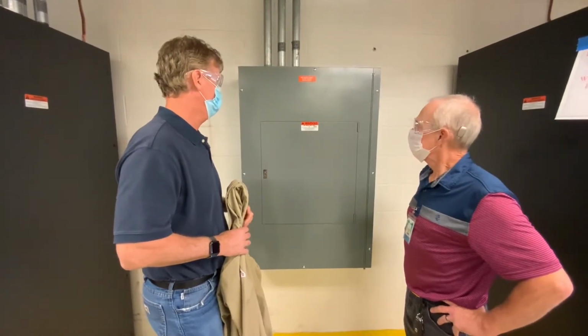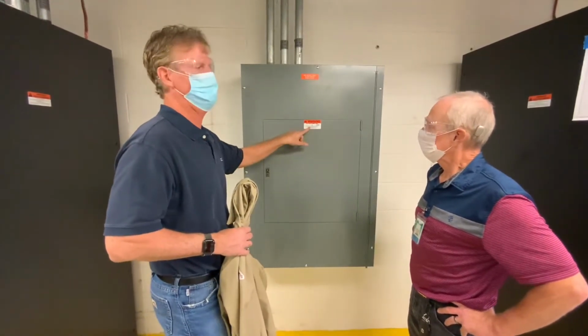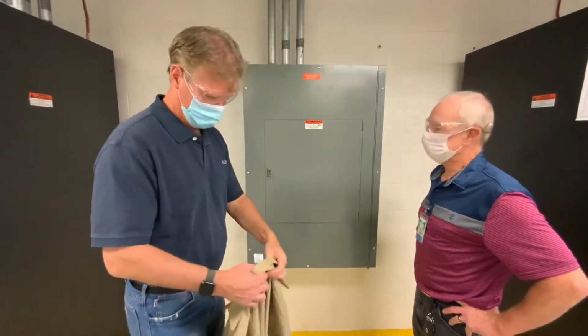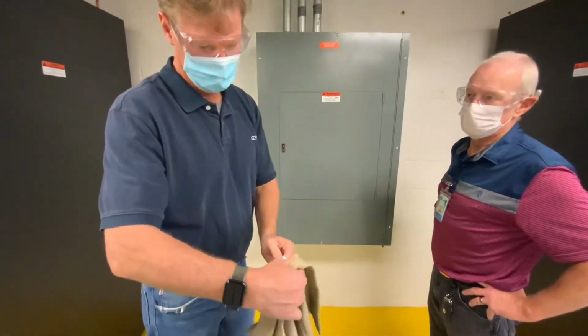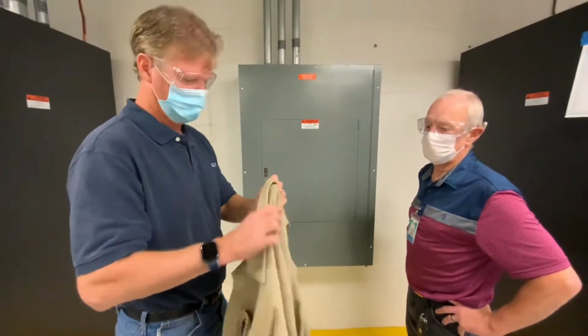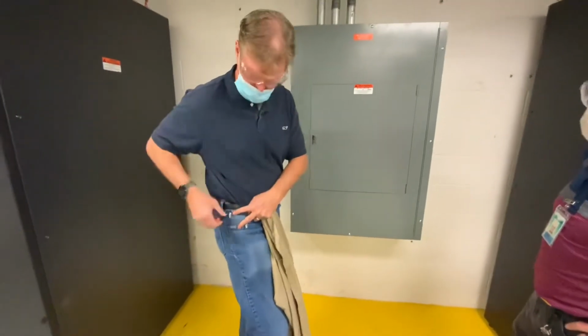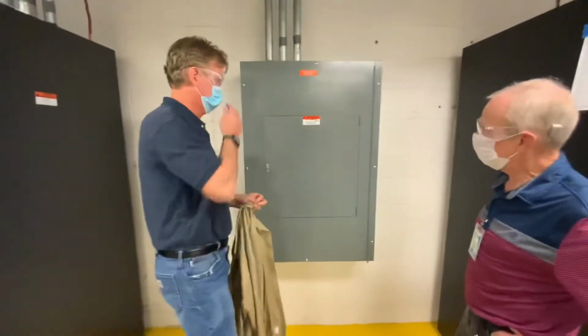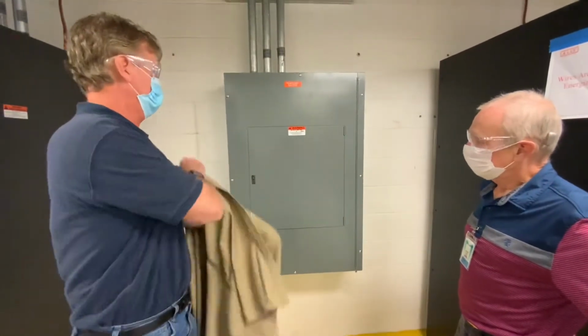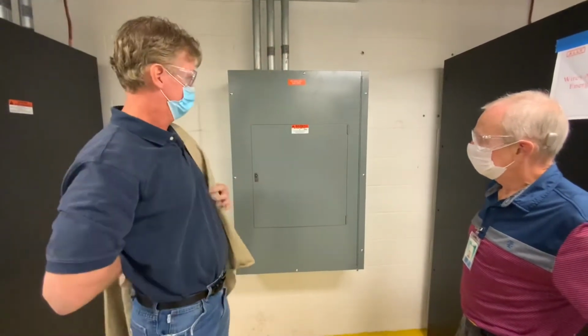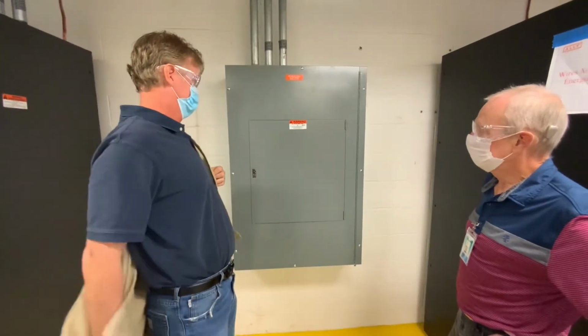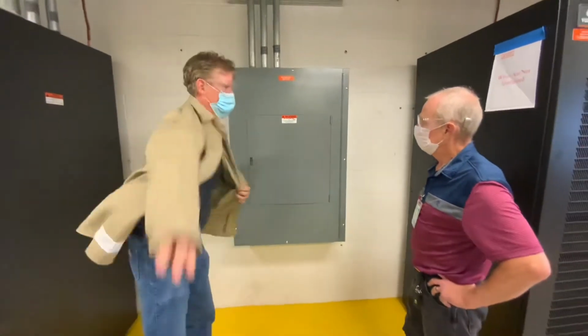As part of your job briefing, discuss the hazards associated with the job or task. What are the voltage levels involved? Is medium voltage involved? Are you working near energized equipment? Are there any secondary or foreign voltage sources or backfeeds possible? Are there any unusual work conditions? Any adverse weather? What are the shock boundaries, both limited and restricted, for the voltages involved?